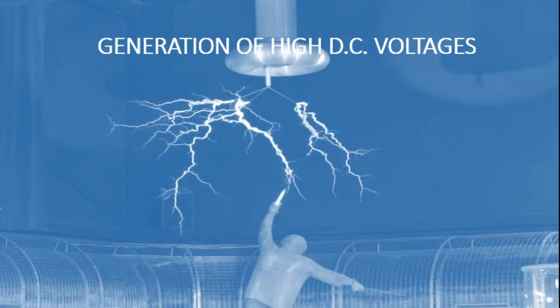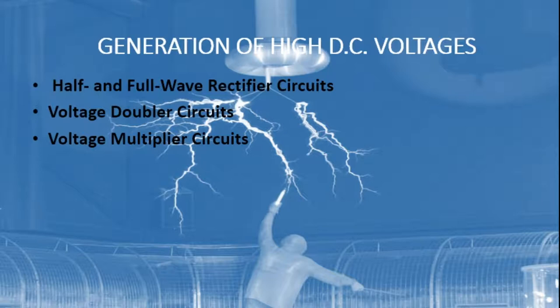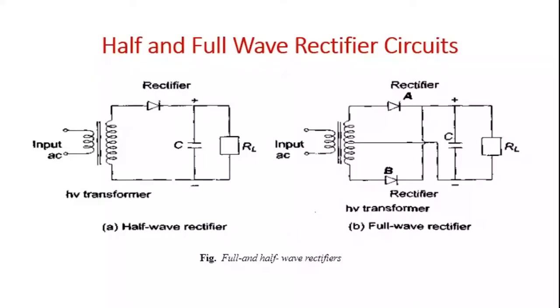For generation of DC voltages up to 100 kV, electron valve type rectifiers are used and the output current is of 100 mA. A rectifier valve requires special construction for the cathode and filaments, since a high electrostatic field of several kV per centimeter exists between the anode and the cathode during the non-conduction period. Methods for generation of high DC voltages include: half and full wave rectifiers, voltage doubler circuits, voltage multiplier circuits, and electrostatic machines called Van de Graaff generators.